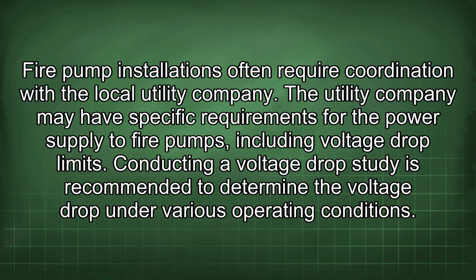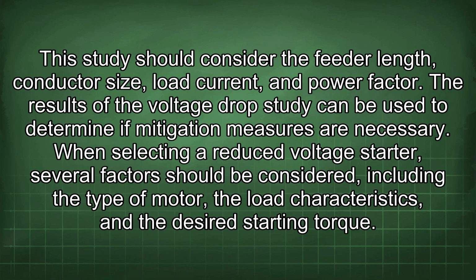Conducting a voltage drop study is recommended to determine the voltage drop under various operating conditions. This study should consider the feeder length, conductor size, load current, and power factor. The results of the voltage drop study can be used to determine if mitigation measures are necessary.